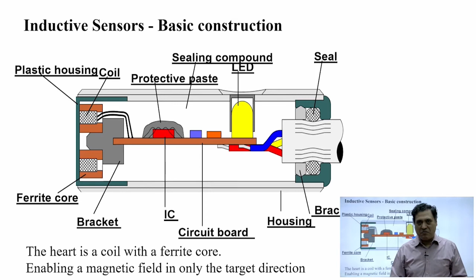So, the heart of any inductive sensor which works for sensing a metallic target is the ferrite core. Let me explain how this sensor actually works. As I said, the inductive sensor consists of four components: ferrite core, oscillator, trigger circuit, and output stage. The oscillator creates a radio frequency that is emitted from the coil. Once the electromagnetic field is emitted, it forms a small lobe in front of it, and when a metal target enters that radiated field, eddy currents are produced inside the plate.